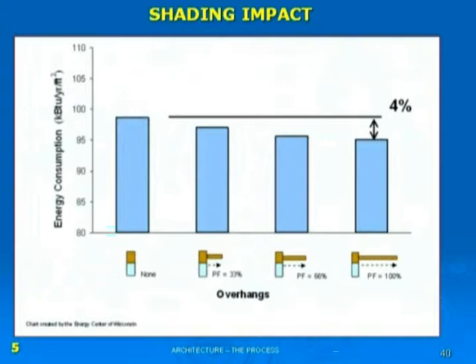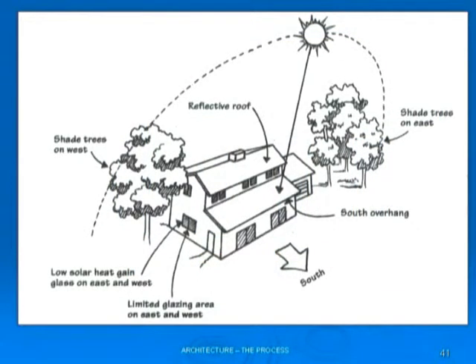Putting it all together: you have a south view with windows that open up to the winter sun. You have some trees on the east and on the west that protect the building from the very low sun angle, because when the sun is very low, a projection is not going to help. Some of the things we look at are low solar heat gain glass on the east and west side. We'll also look at reflective materials or light-colored materials on a roof to reflect the heat, as opposed to dark color which absorbs that heat.